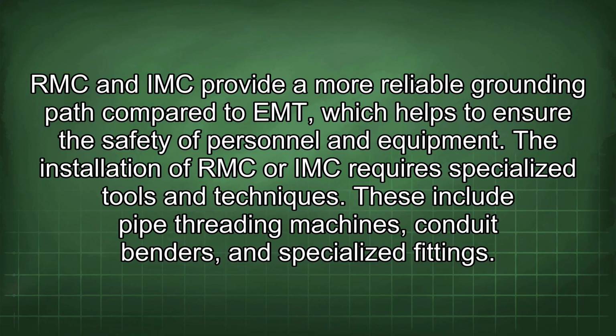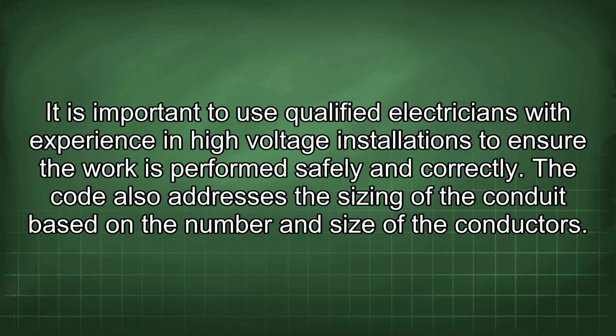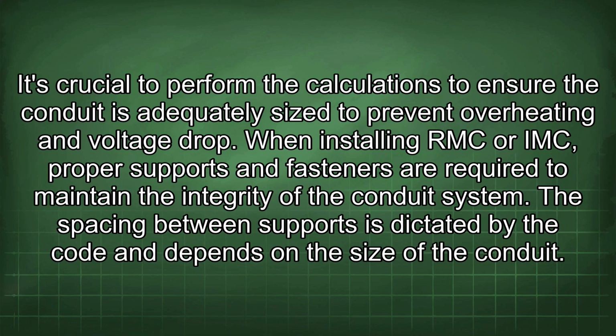and equipment. The installation of RMC or IMC requires specialized tools and techniques. These include pipe threading machines, conduit benders, and specialized fittings. It is important to use qualified electricians with experience in high-voltage installations to ensure the work is performed safely and correctly. The code also addresses the sizing of the conduit based on the number and size of the conductors. It's crucial to perform the calculations to ensure the conduit is adequately sized to prevent overheating and voltage drop.